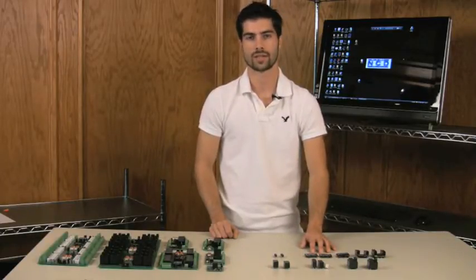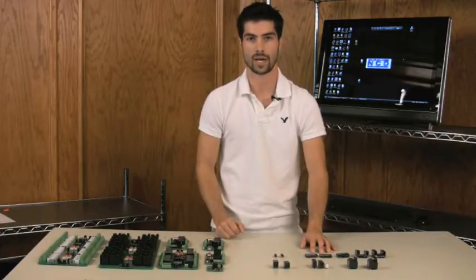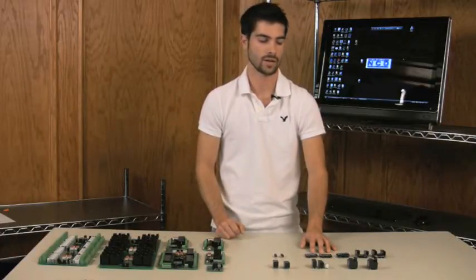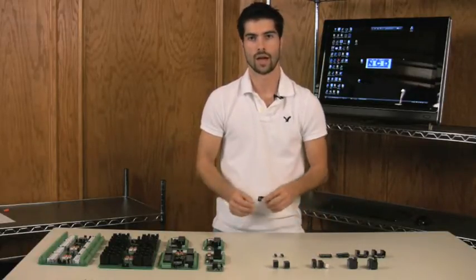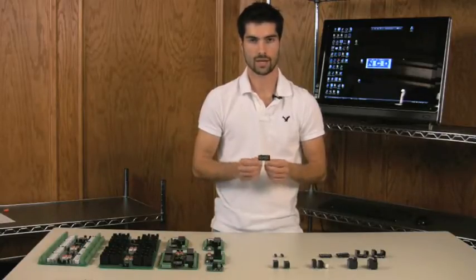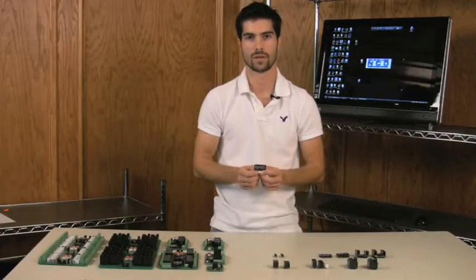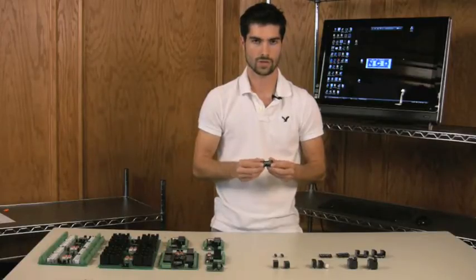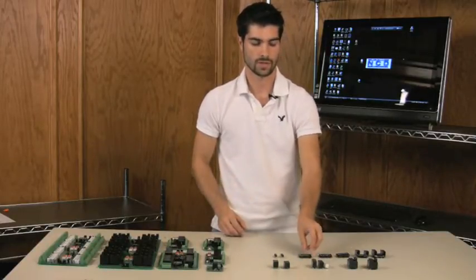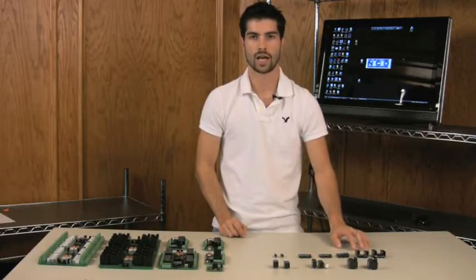Whenever you go to select a solid state relay controller on our website, towards the bottom of the page it will ask you which type of solid state relay you want. Be sure and review all of the information. These things have what we call a minimum switching current, meaning they are load dependent. You can't switch, I believe all these have a minimum load of .06 amps, so you want to make sure that you're switching more than that whenever using these. So you want to review that, you want to know whether or not you're switching resistive or inductive loads, and you'll have to know the amperage of the device that you're switching.